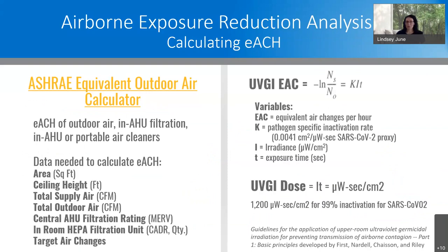There are several open source tools that have entered the market since COVID that calculate EACH and that were used in the studies. One such tool was used by multiple consultants in our studies, and it's the equivalent outdoor air calculator developed by ASHRAE's Epidemic Task Force. While it was developed to determine the time required to achieve target air changes for a building flush, the tool does calculate EACH values for outdoor air, in air handling unit MERV filtration, and in handling unit or portable air cleaners. The tool tallies those EACH numbers for strategies employed from this simple set of data points noted here on the slide.